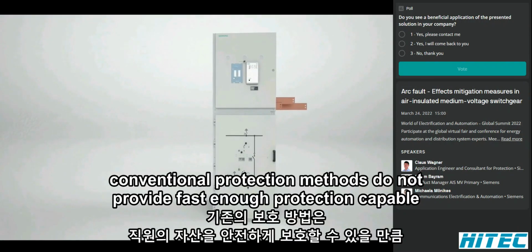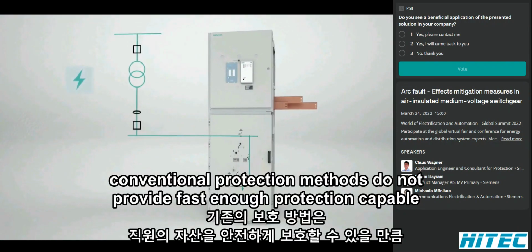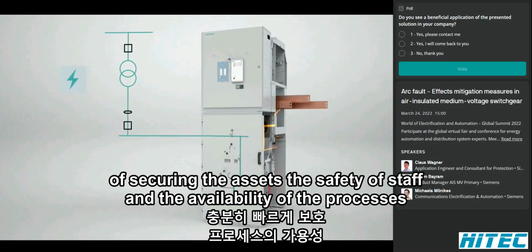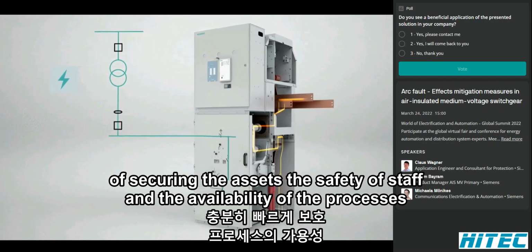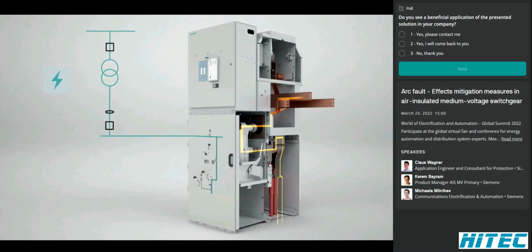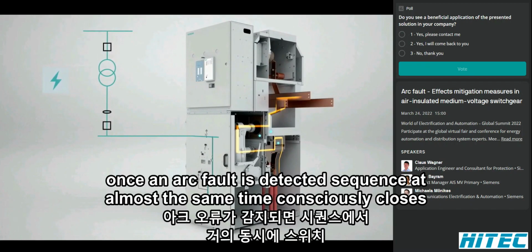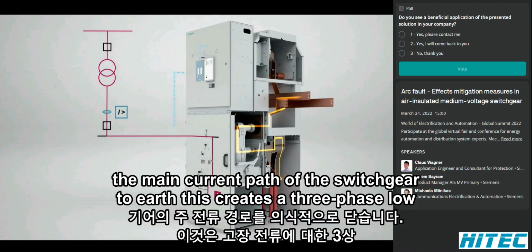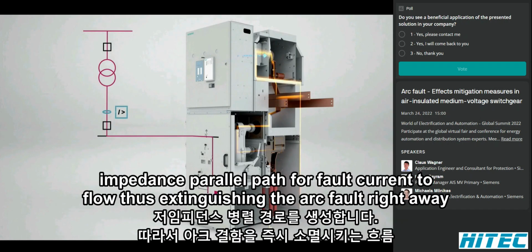Conventional protection methods do not provide fast enough protection capable of securing the assets, the safety of staff, and the availability of the processes. Once an arc fault is detected, SIEMENS, at almost the same time, consciously closes the main current path of the switchgear to earth. This creates a three-phase low-impedance parallel path for fault current to flow, thus extinguishing the arc fault right away.